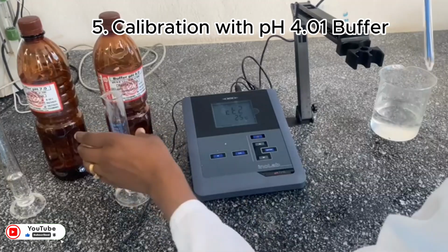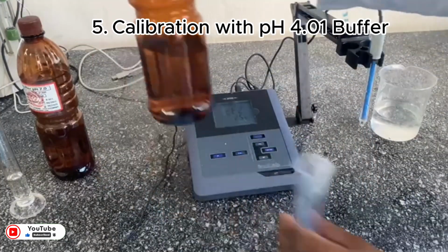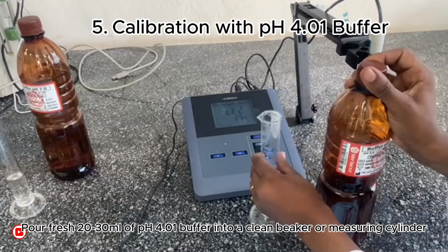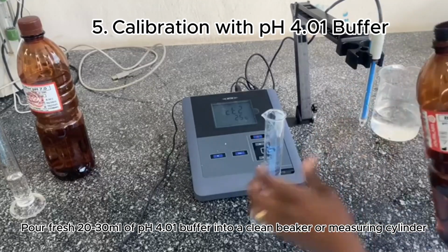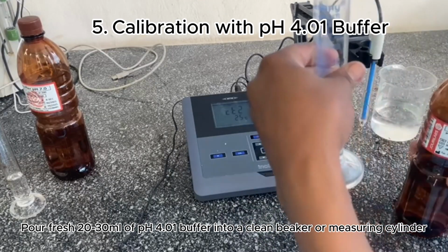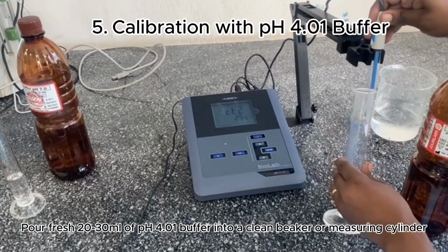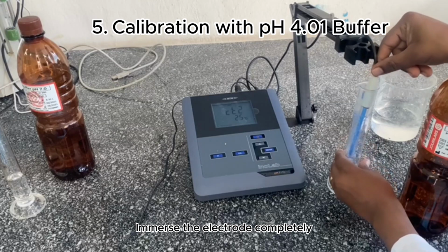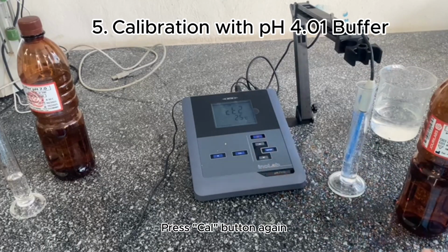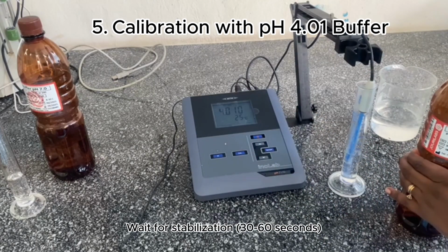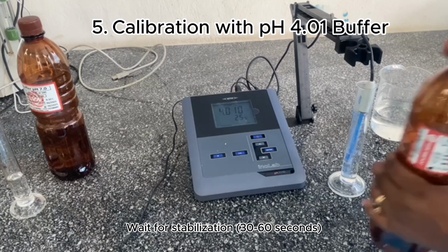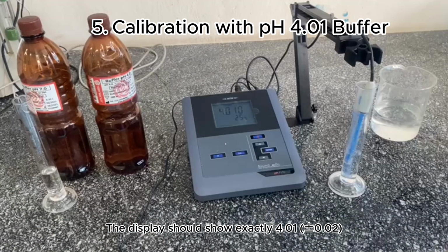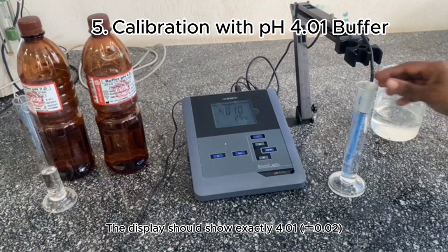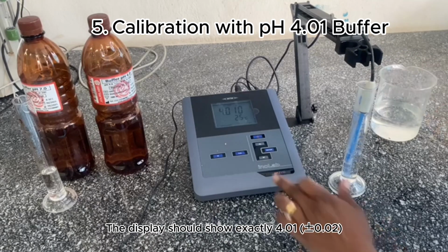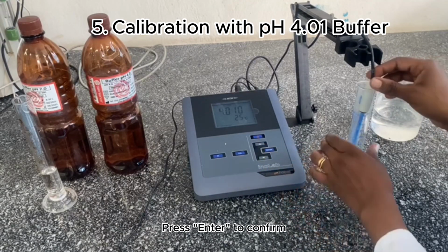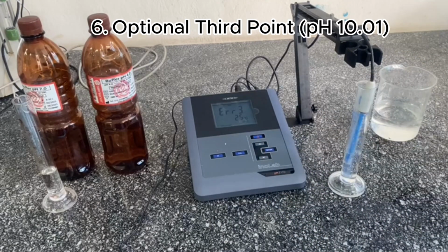5. Calibration with pH 4.01 buffer. Pour fresh 20 to 30 milliliters of pH 4.01 buffer into a clean beaker or measuring cylinder. Immerse the electrode completely. Press Cal button again. Wait for stabilization, 30 to 60 seconds. The display should show exactly 4.01, plus or minus 0.02. Press Enter to confirm.